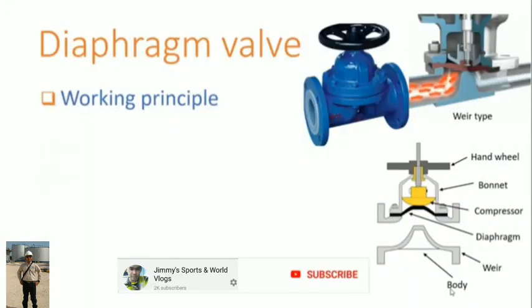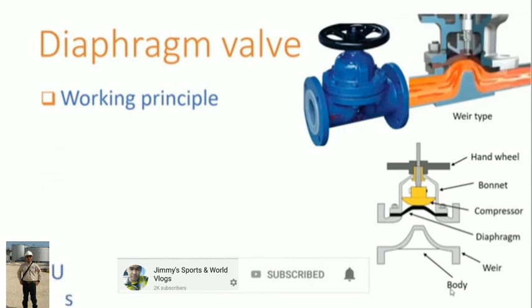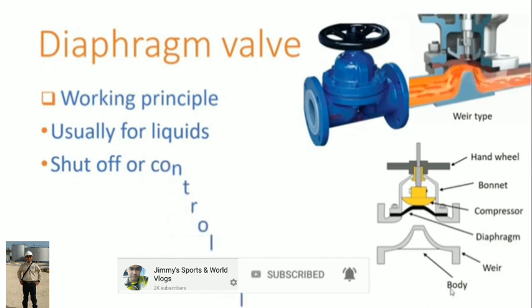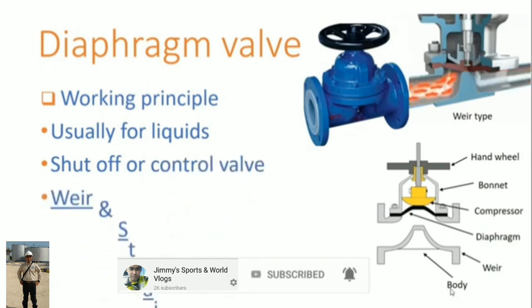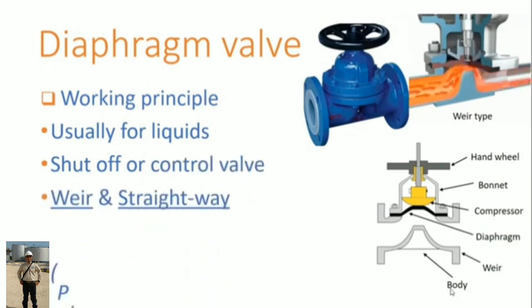Diaphragm valve working principles. It has a diaphragm moved by a compressor with the aid of a stem. Most of the time it uses for liquids, acting as both shut-off valve and control valve. There are two types called as weir and straightway. Most commonly seen is the weir type. The pinch valve is an improvement of the diaphragm valve working on the same principle.